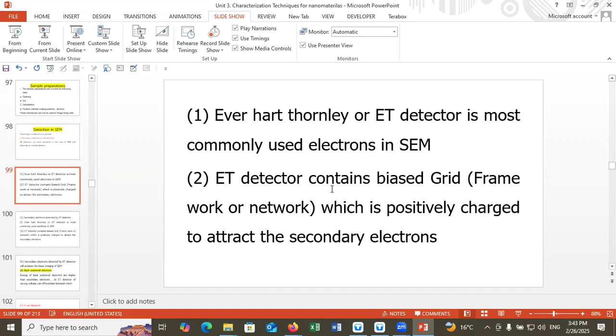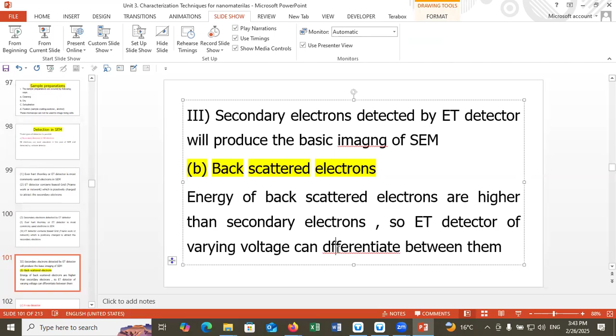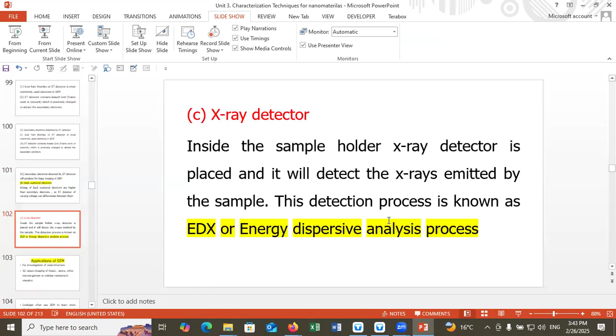Backscattered electrons. The energy of backscattered electrons is higher than that of secondary electrons, so the ET detector is used with varying voltage difference between them. X-ray detector: inside the sample holder, an X-ray detector is placed and it will detect the X-rays emitted by the sample. The detection process is also known as EDX or Energy Dispersive X-ray analysis.